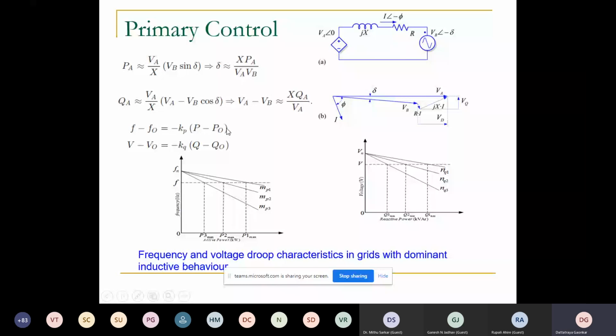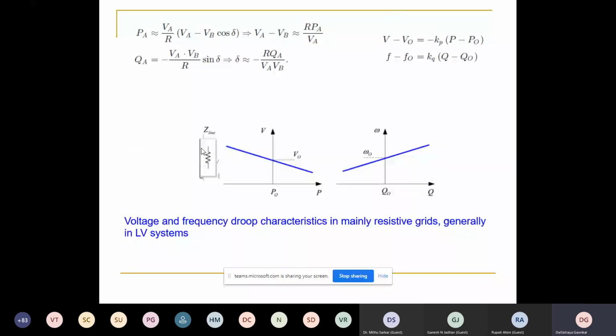In the conventional grid, we assume the line is more inductive than resistive, but that is not so in a distribution network. In a conventional grid, you can control the frequency by controlling the active power droop and the voltage by controlling the reactive power droop. But that is for the transmission network, which is more inductive, whereas distribution is more resistive. Exactly the reverse relation holds. By controlling the active power, you control the voltage. By controlling the reactive power, you control the frequency. That is how it will operate.